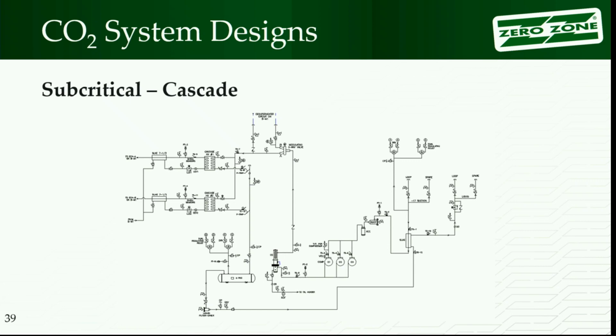This guy here, interesting, we talk about serviceability. If I wanted to change the suction filter, right? That sounds like something we might want to do a couple days after startup, whatever. I'm going to need to isolate it. It doesn't show up here, but these compressors actually do have isolation valves on them. There's an earlier drawing. We're going to isolate at the compressors, that sounds good. And I'm going to go over here and isolate on my suction lines, right? You notice that little oddity on there? Not really. A little bit hard to see.